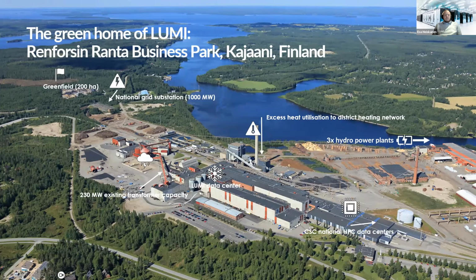So excess heat utilization was a pretty clear solution and option when operating in this business park area, because we have this district heating power plant only a couple of 100 meters away from our data center. So excess heat utilization is pretty cost effective to do. This area has this national grid substation with almost 1,000 megawatt installed capacity from 6 different directions from national grid. And in this area we have already installed 230 megawatt of existing transformer capacity, which is already in place. So this is pretty solid in the network power distribution wise for this kind of HPC operations that Lumi is.